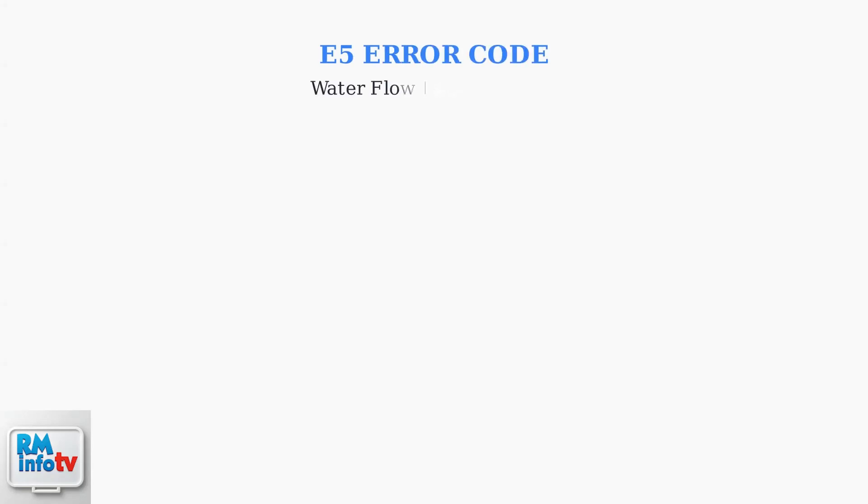The Rheem tankless water heater E5 error code indicates a water flow issue. This error typically means the flow rate is too high or there's a problem with the heat exchanger, a blockage, or a faulty sensor.